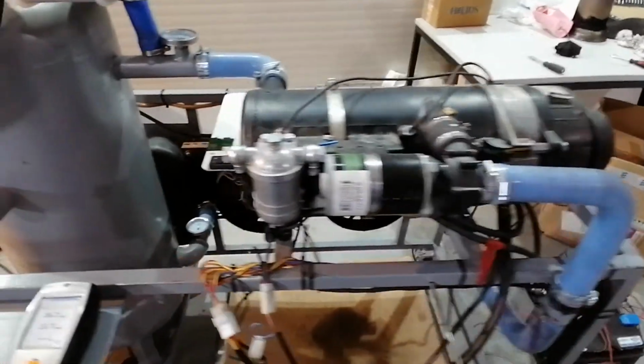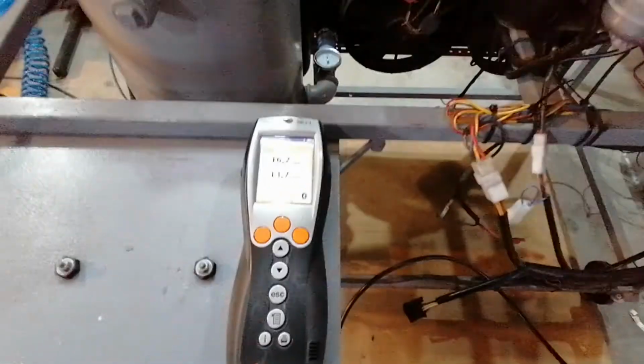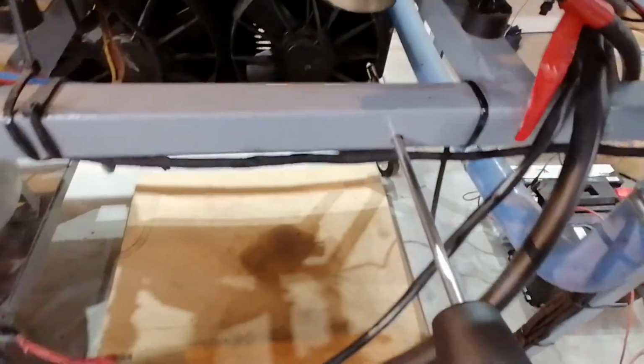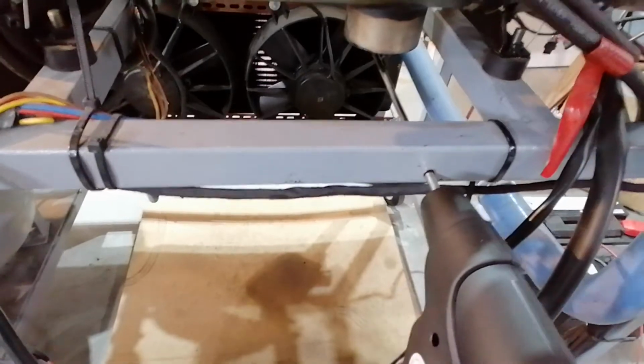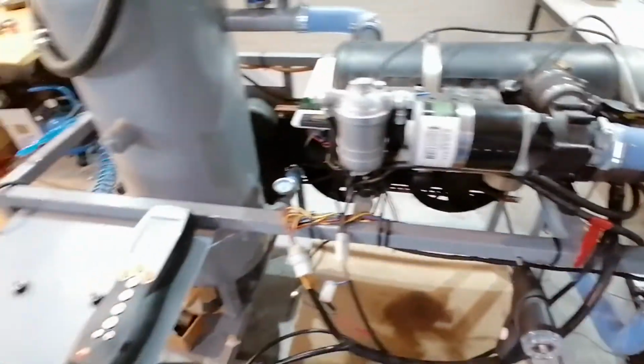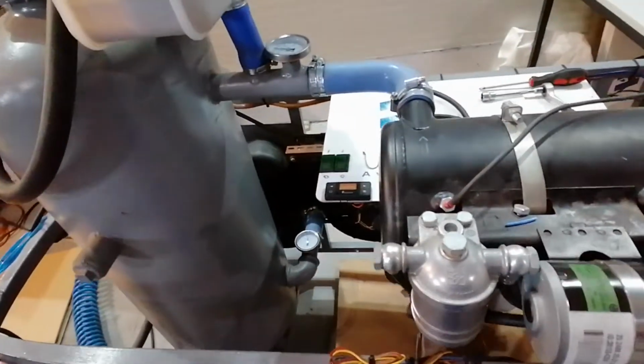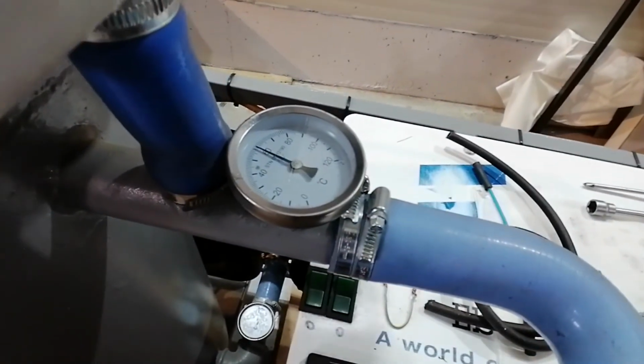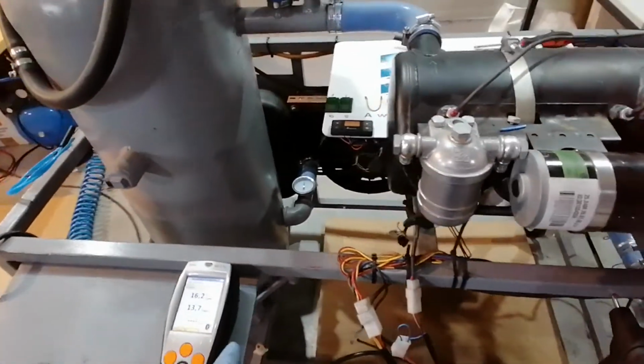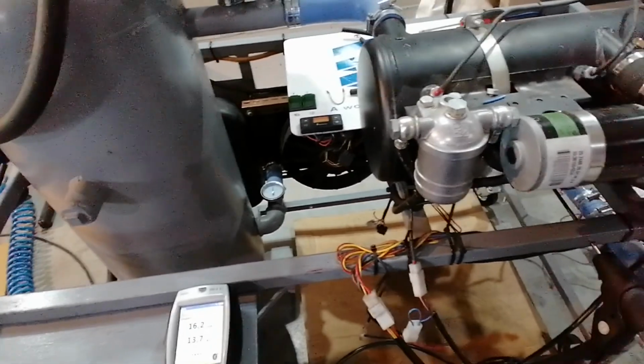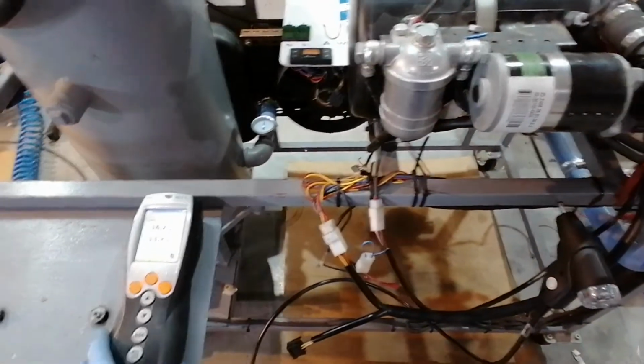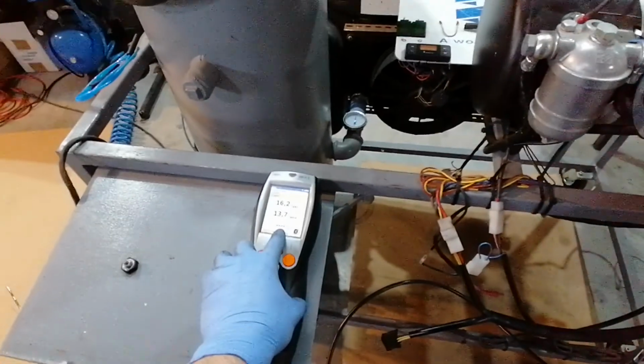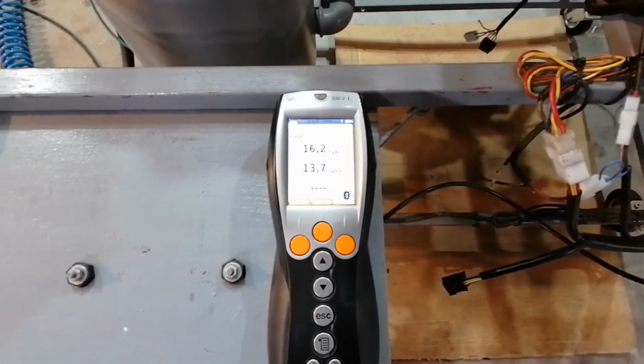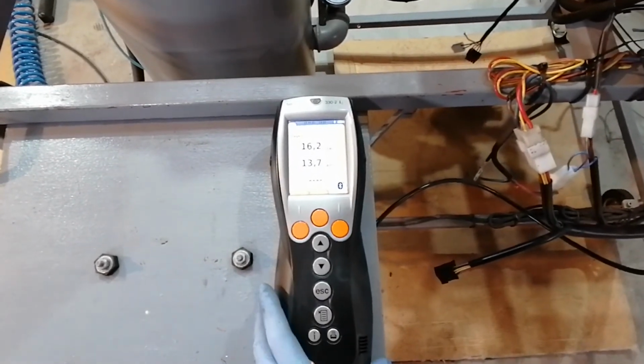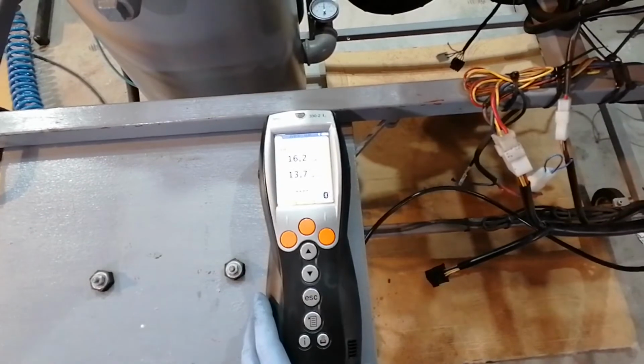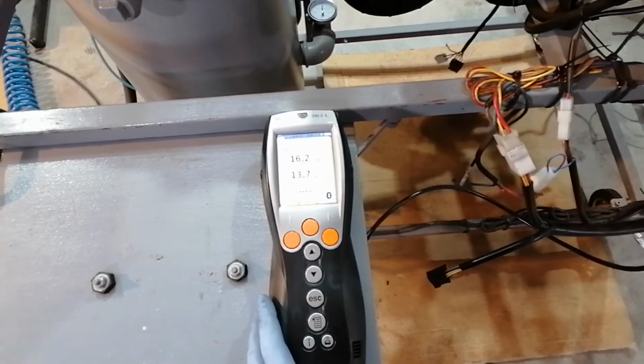Okay, so we started the unit again. I brought my gas analyzer, which normally goes right here in the exhaust, right in the middle. I will start the measurement as soon as the water temperature reaches about 70 degrees, and then I'll start the fans, so it will be pretty loud. The idea is to get the CO2 percentage somewhere between 9 and 11%, which is what the manual recommends for this unit.